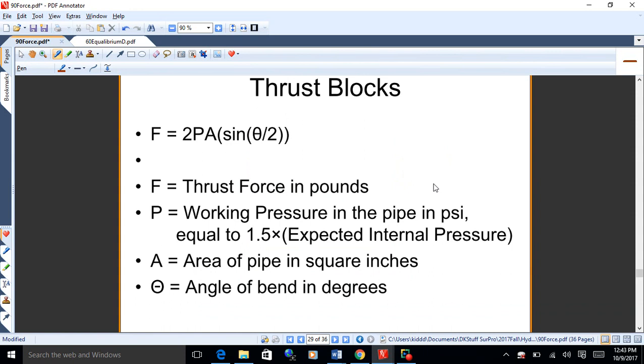This is called the working pressure, or actually the working force. What you're doing here is turning bends with these pipes, usually. So you're getting two forces that enter into it. You want to calculate what you call the resultant force, which would be going off that way. It's the combination of the two you've generated. This involves a little bit of trigonometry, and I won't get into the derivation of the formula, but what you end up doing is taking the sine of half the bend angle.